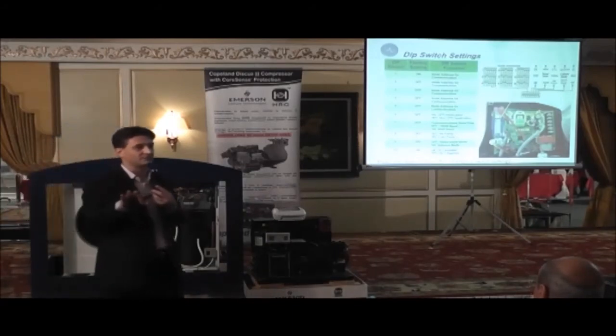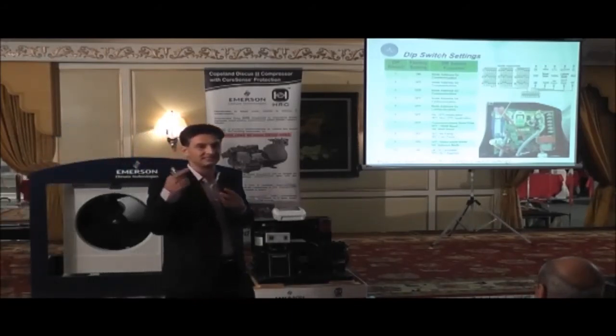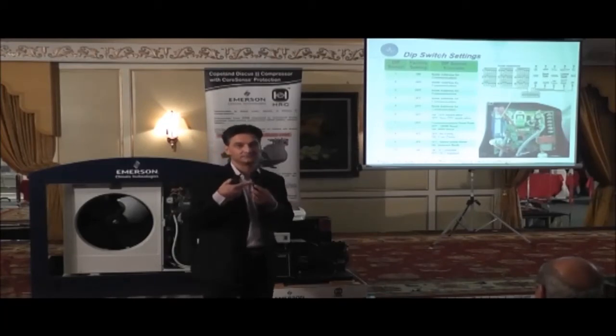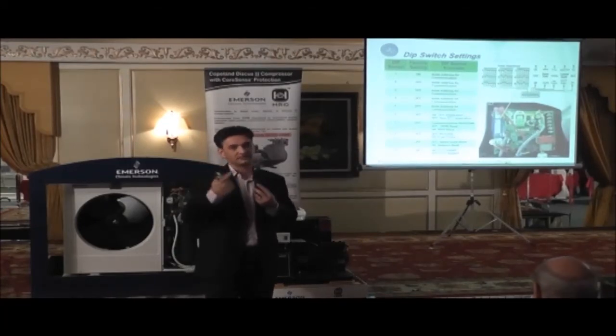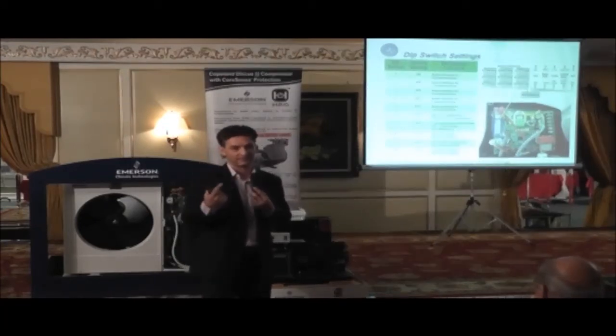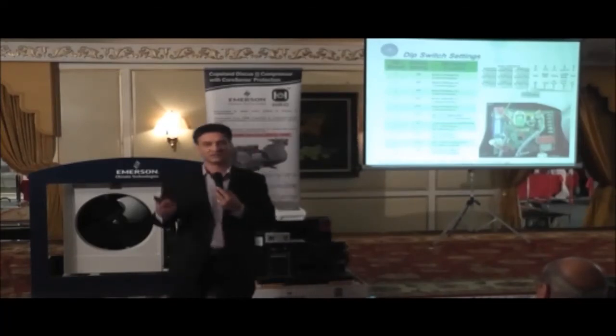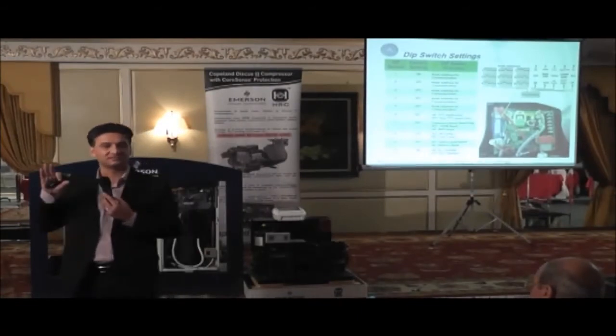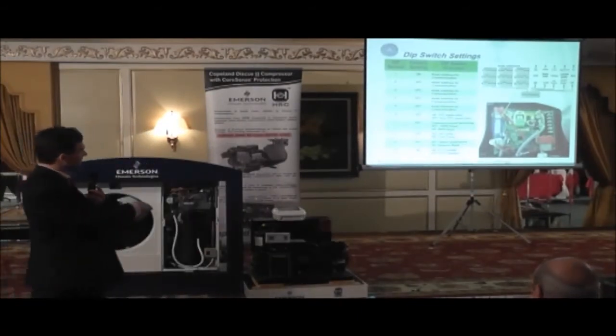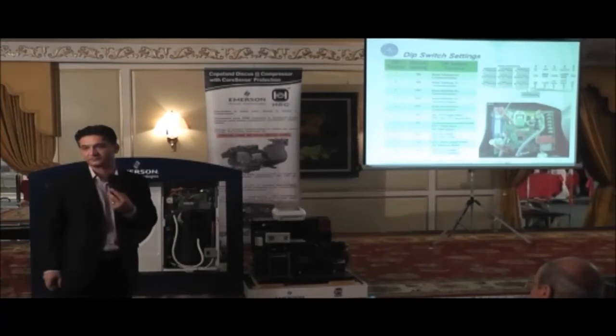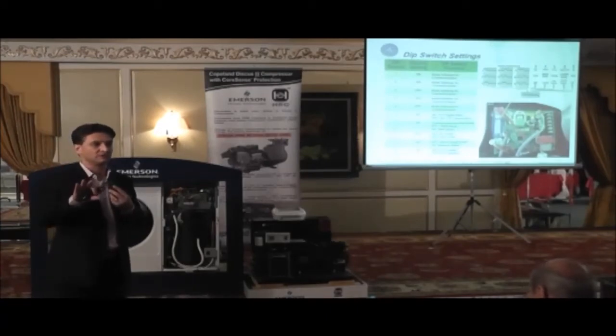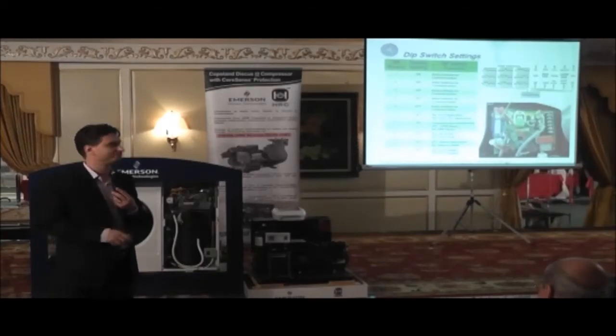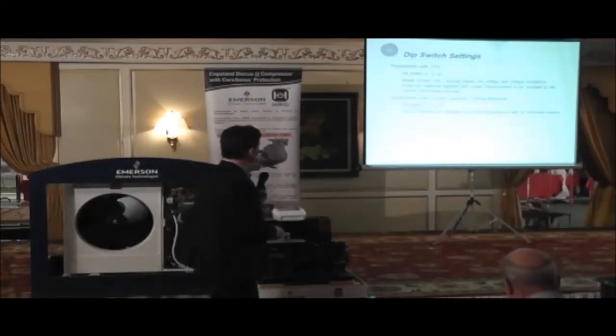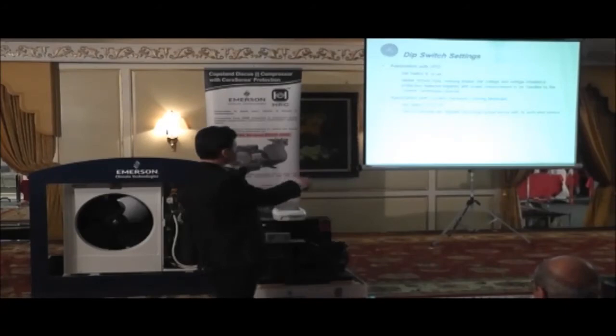Is any of you familiar with demand cooling? The demand cooling module has its own NTC sensor. Alright? So we don't want the two modules to be competing with one another. So one has to become the master. So in condensing units, when you buy condensing units that are fitted with demand cooling, this dip switch will be set to off so that the demand cooling module takes control of protecting the compressor. That's basically summarized on these sheets.